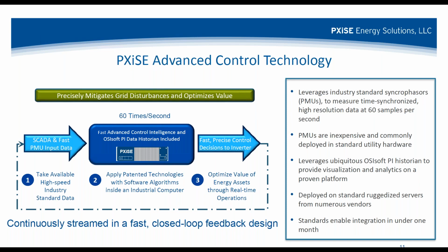What it does is get data from the synchrophasors, using them as sensors every cycle. So 60 times a second we're getting data on the exact state of the grid as seen by the synchrophasor. Our engine crunches that very quickly and determines where it's off the exact requirement, whatever the set point is, bought by the needs of the grid, or set by the utility, or by the C&I customer. Then it figures out what it should be, and sends new real and reactive set points to any of the inverters on the system.